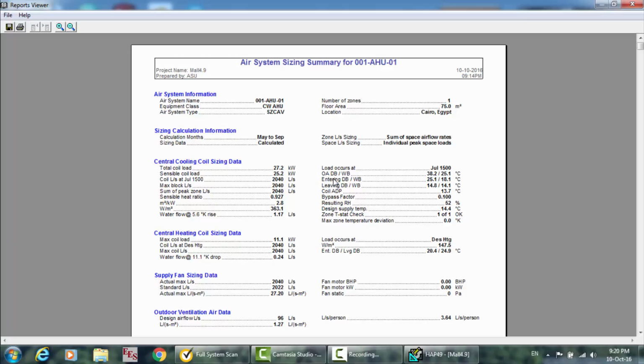And here the outside air dry bulb, wet bulb. This is the outside air, wet bulb and dry bulb. The entering dry bulb, wet bulb. This is the temperature of the air that enters the cooling coil. It is at 25.1. It is higher than 24 because, as you know, the return air from the zone is predicted to be at 24 or larger than it, and there are losses, and the return air gains heat from the plenum or from the losses at the duct, so it is predicted to be larger than 24.